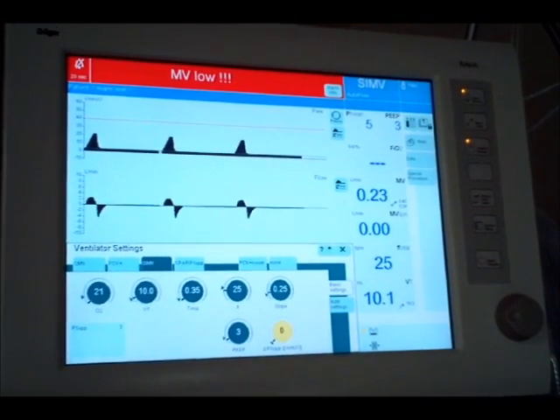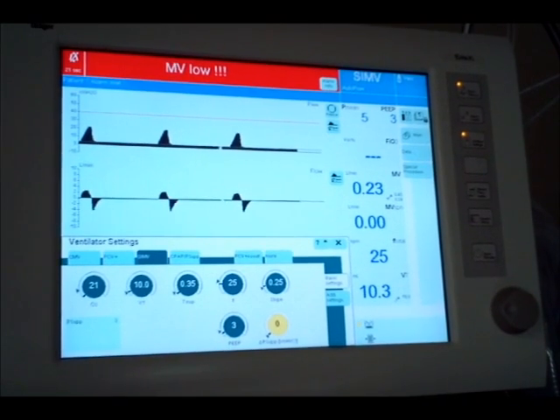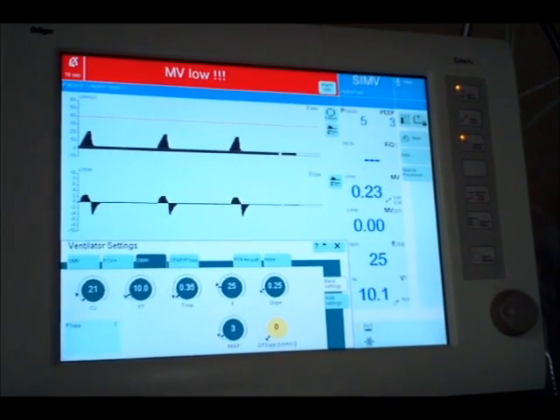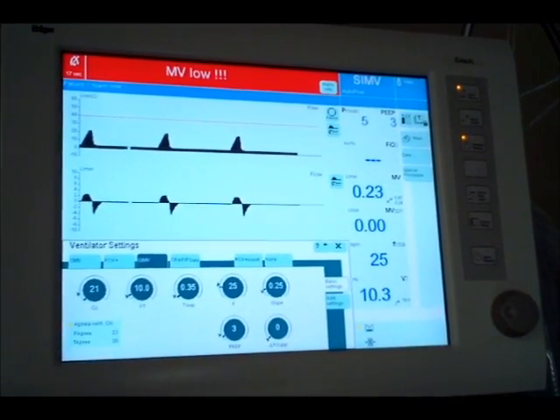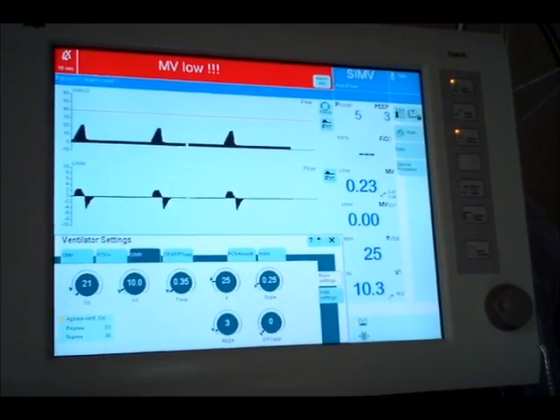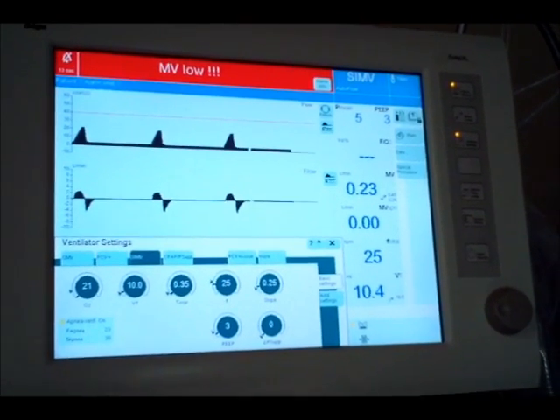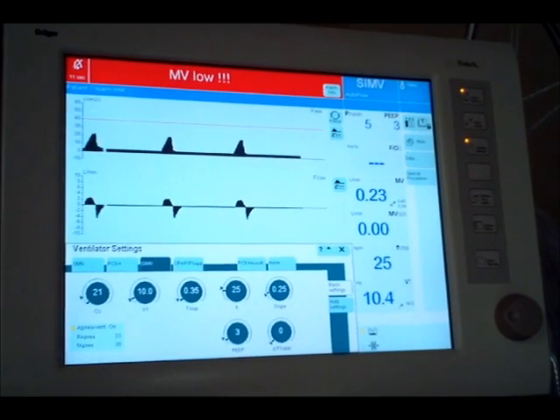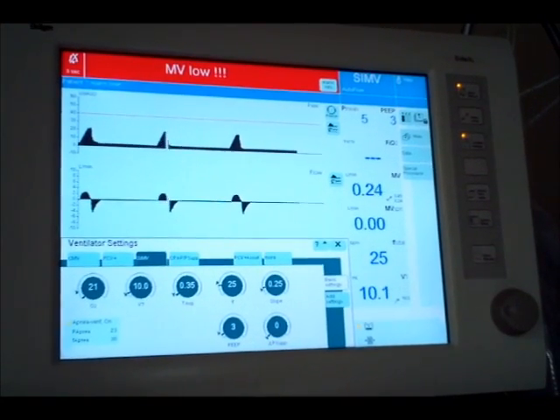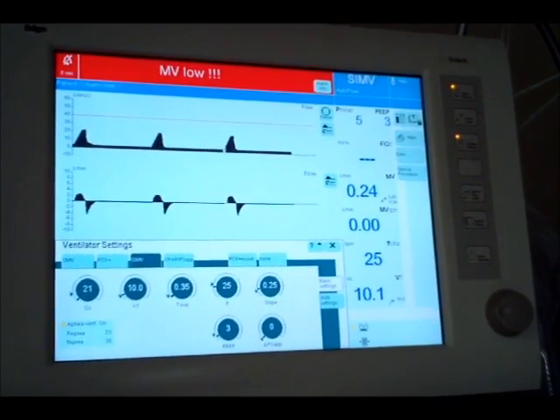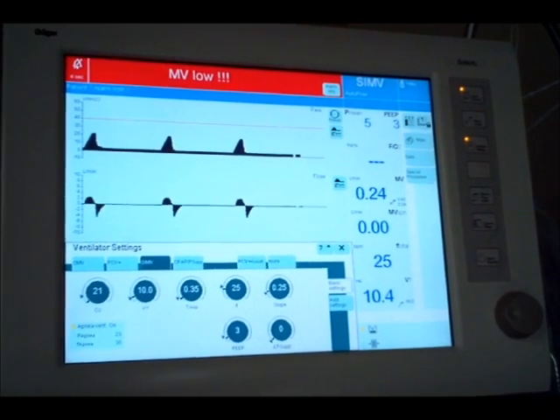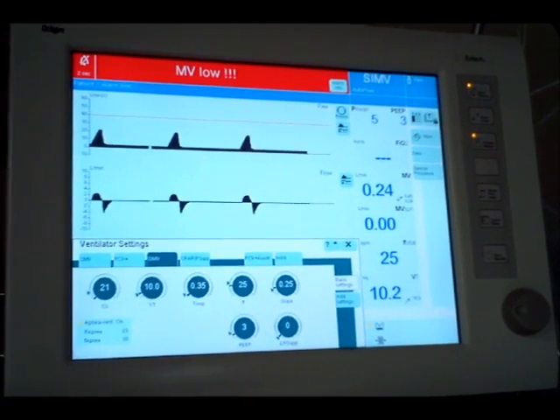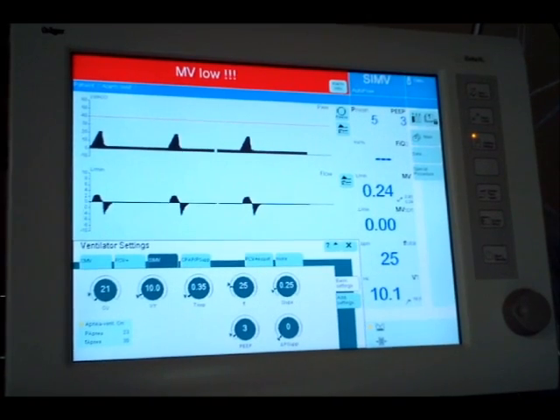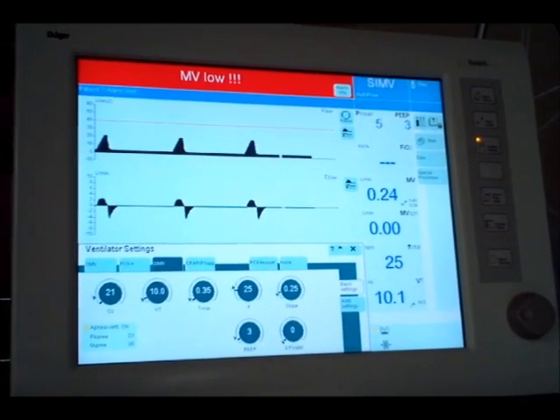Looks pretty good still, I think. Am I getting my tidal volume okay? If I'm not getting my tidal volume, that's when I start messing with the slope and the inspiratory time. But I want a tidal volume of 10, right? And I'm getting 10.4, 10.3. Notice, some of you will probably give a sigh of relief, but you're not going to be turning that PIP knob to try to get that tidal volume just where you want it. Set tidal volume to 10, kind of forget about it.